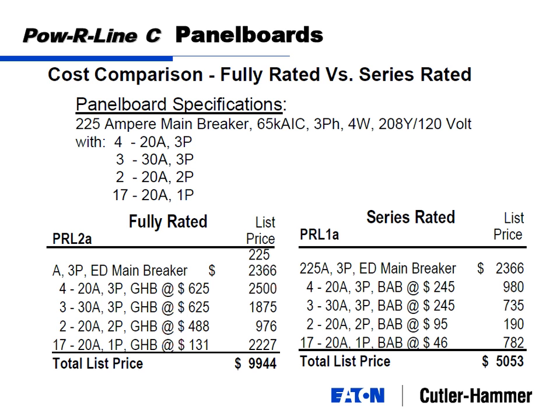Why would you ever use series rated versus fully rated? Most engineers, they use fully rated. That's all they'll do. They just know that if they're signing their name to a document, they don't want the value engineering saving of series rated. They want the fully rated, and just don't trust the UL tested combinations, and that's fine. But if you're looking for cost-effective alternatives and you need to find $1 million in cost savings, or the project's going to go under and you're not even going to build nothing, one of the ways you can do is look at the panel boards and look at series rating.